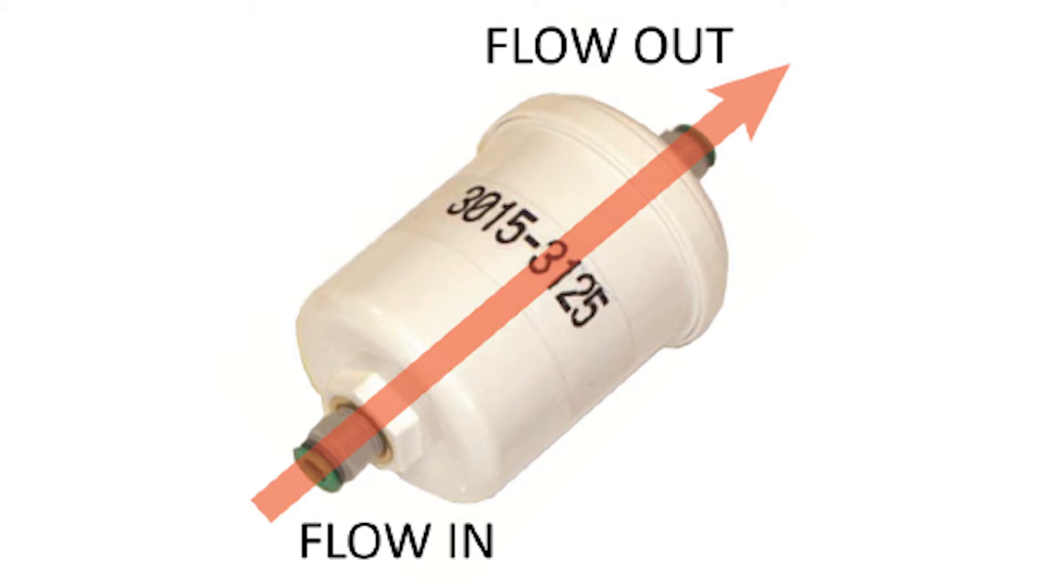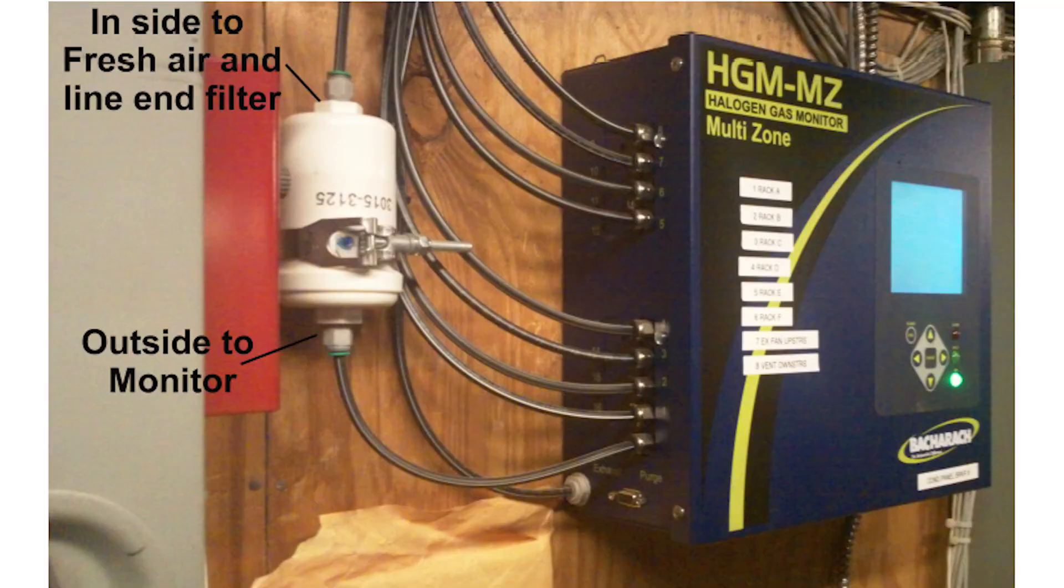Use tubing to connect the inside of the charcoal purge filter to the fresh air line in filter. If the charcoal purge filter is mounted inside, do not mount the filter in any area with ambient refrigerant contamination. This will cause the filter to fail.